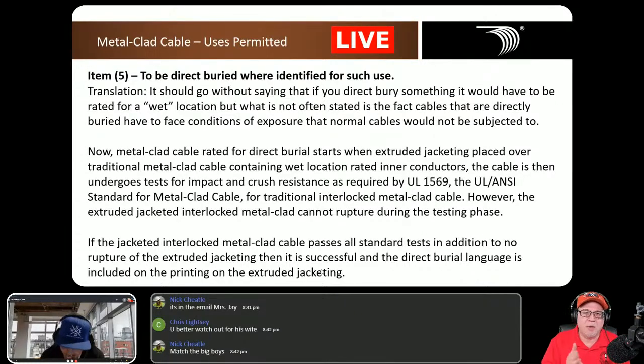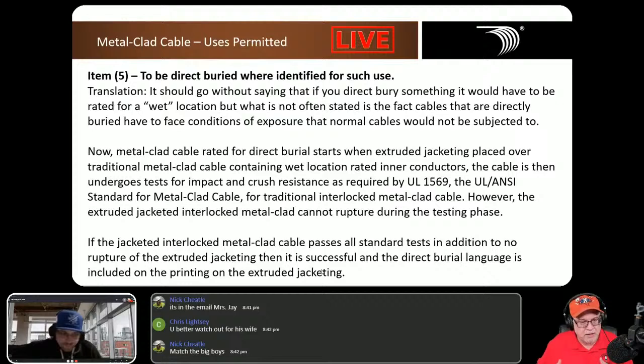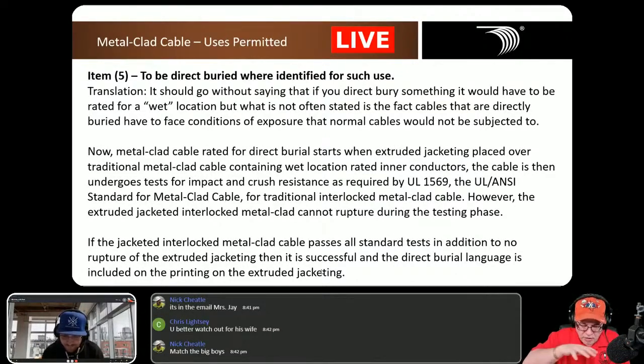It should go without saying that if you direct bury something, it has to be rated for a wet location. Everything covered under 300.6, whether outside or in the ground, is going to be a wet location. It doesn't matter if it's liquid tight, what raceway it is, or if a cable is listed for use outside, it's going to be a wet location, so the conductors inside will have to be wet location rated. That should be a given, right? But in order to be rated for direct bury...